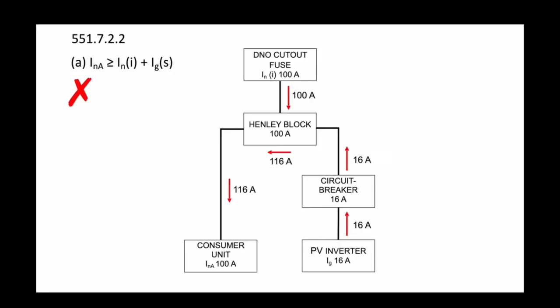Can you solve it for me? Yeah, there's several ways you can solve it. So you've already come up with one way. Another way could be to replace your friend's consumer unit with a 125 amp device. So, that's a good point - is that an easy thing for manufacturers to have? If their consumer unit is rated 100 amps, how hard would it be for them to rate it 125?